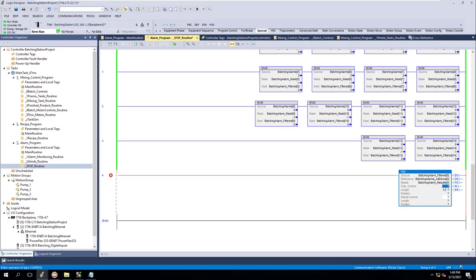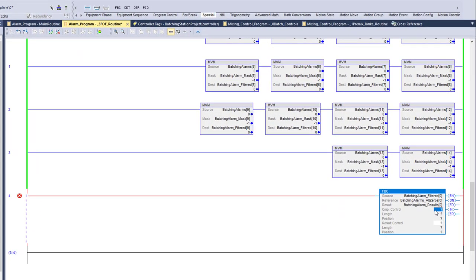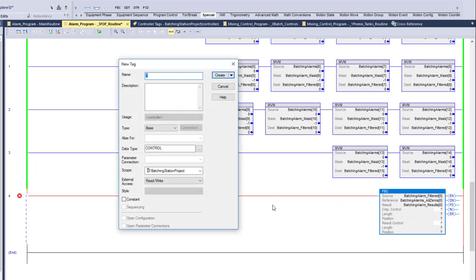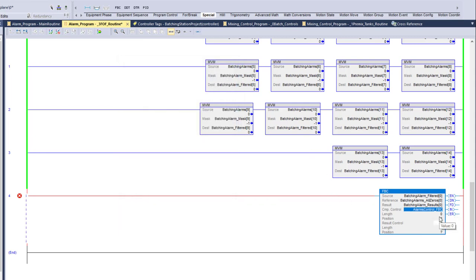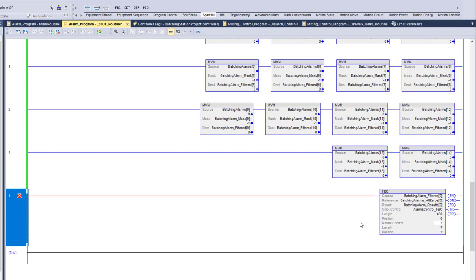Now we get to the comparison control — this is the actual instruction name. We're going to call this 'batching alarm control FBC.' That comes in here, and now we give it a length. We want our length as 480 bits because that is the finite number of bits we want to monitor. Per design: if you're designing for 32 bits you put 32, for 480 bits you put 480.